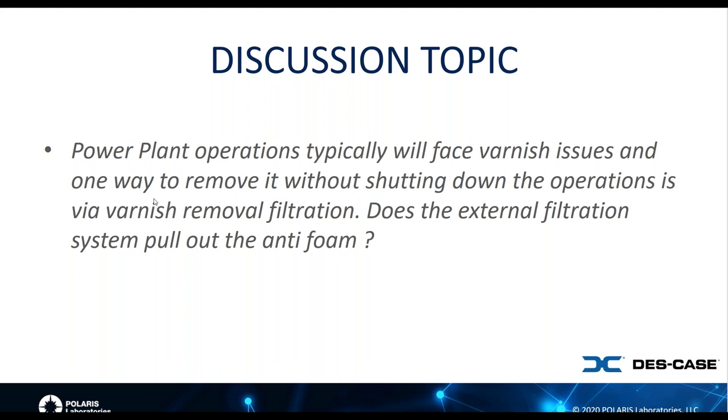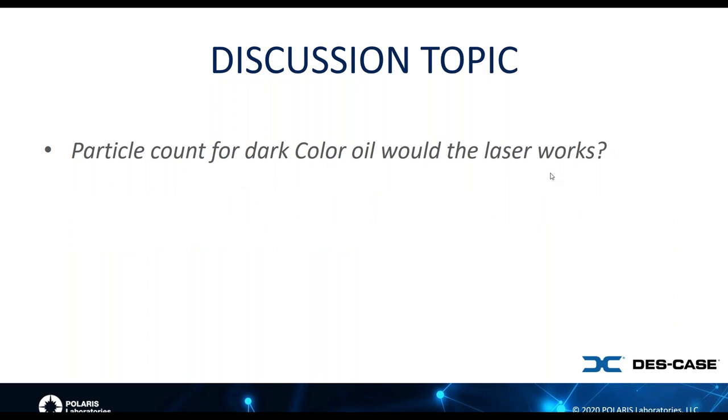Okay, so what do we have next here? Particle count for dark color oil, would the laser work? That answer is maybe, depending on how dark the fluid is. We don't do particle counting for our diesel engine oils just because they are black, and that does become a difficult problem. But we do have methods for diluting down some of the darker oils to still get counts. You just want to make sure you're using particle counting for an appropriate component type. Not necessarily a good option for your diesel engine, but probably a lot better option for your hydraulic fluids. Julio, what do you think?